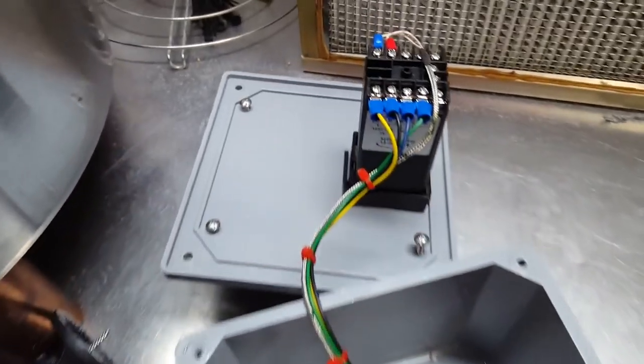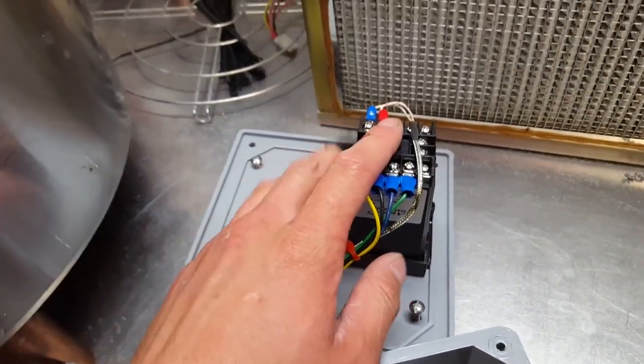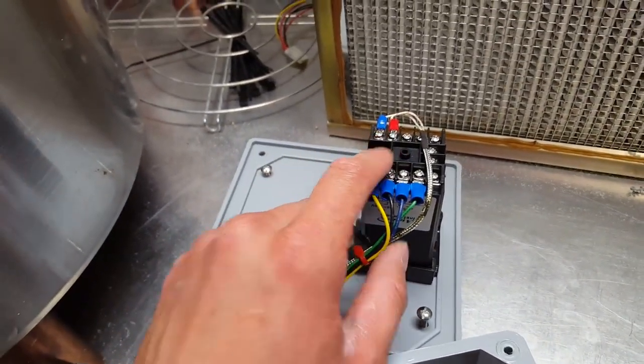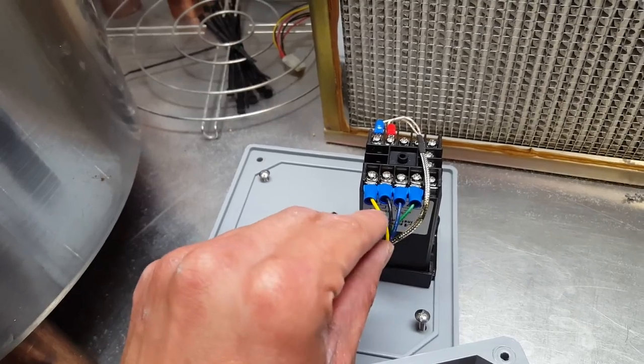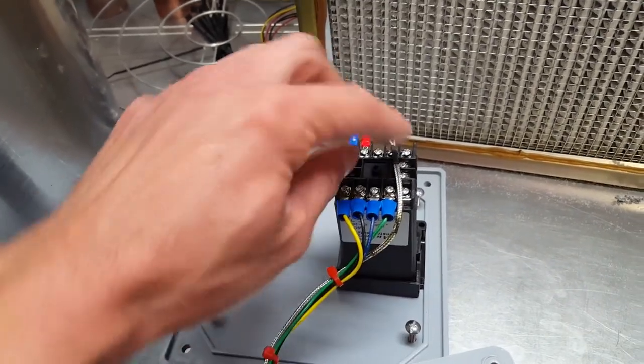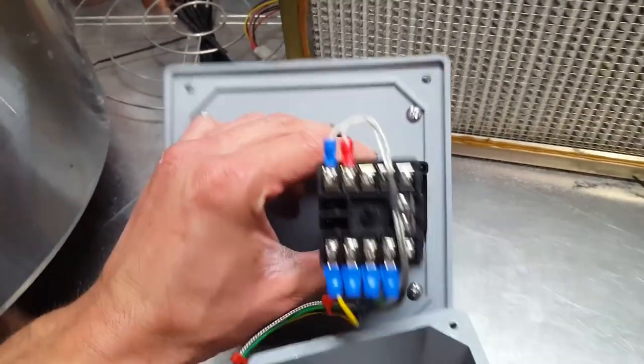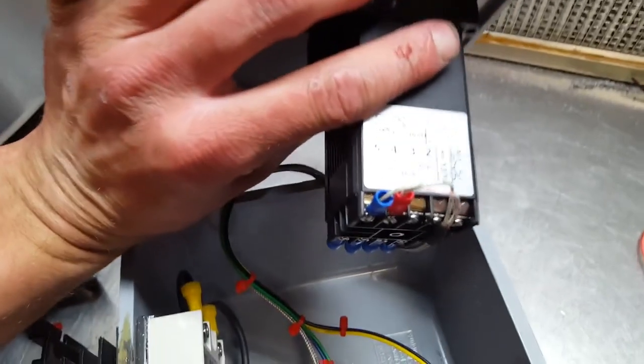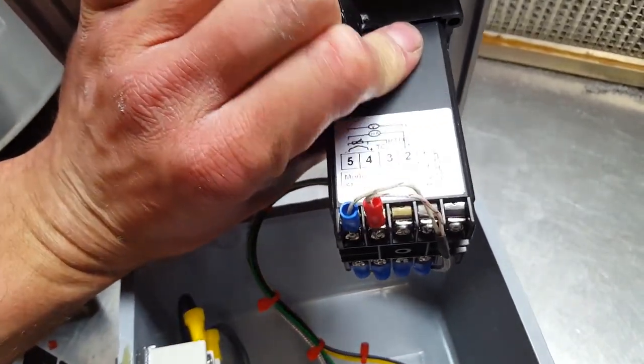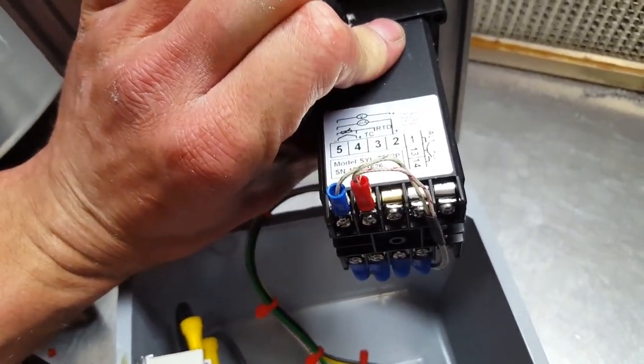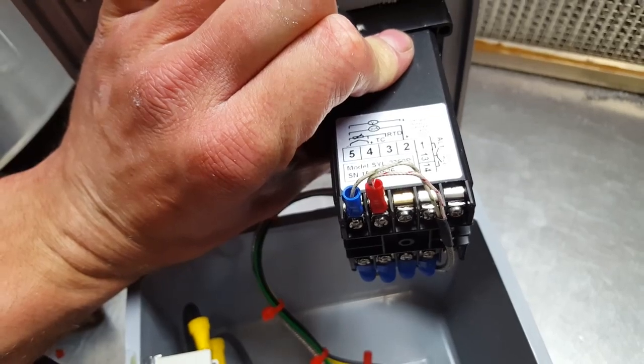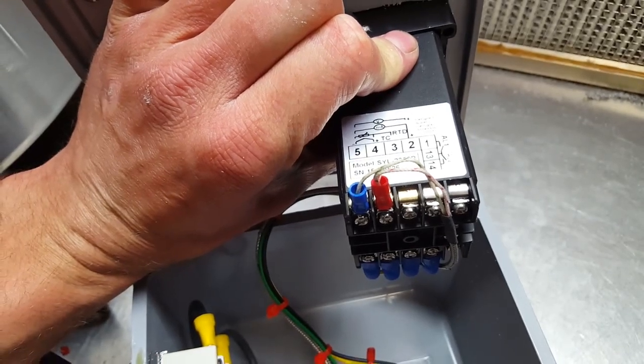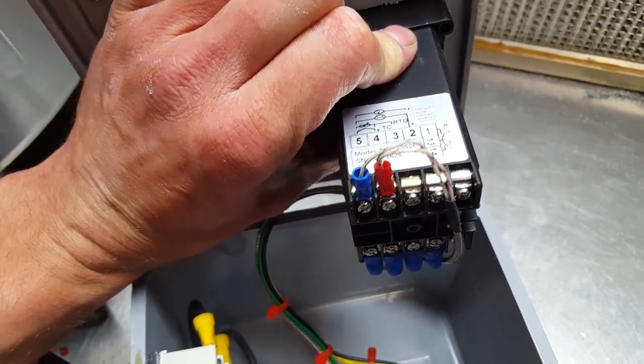The wiring is fairly basic. The PID doesn't get any big wires, they're all small 18 gauge wires. You have the sensor. The temp sensor goes to what is marked as TC plus and minus, and the negative goes to the blue and the positive goes to the red.